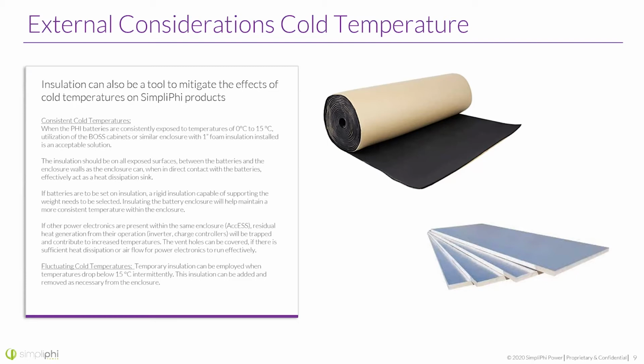temperature. If batteries are to be set on insulation, a rigid insulation capable of supporting the battery weight needs to be selected. So, here's some ideas of a rigid insulation, and that's always important when looking at something that's going to be weight bearing. If other power electronics are present within the same enclosure, so for instance, our AccESS unit, our all-in-one ESS, residual heat generation from those different components, like the inverter and the charge controller, will be trapped and contribute to increased temperatures.